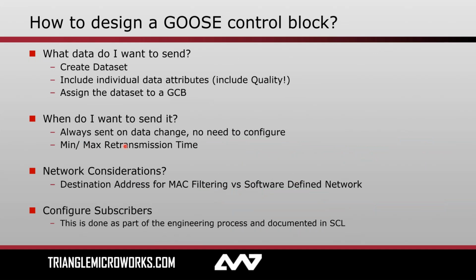So now let's talk a little bit about, like we did for report control blocks, what do you need to do if you're someone coming in and designing a substation, designing the GOOSE in it? What are the things that you need to keep in mind? Well, first, just like we had for reports, you need to design your data set. What information do I need to accomplish my larger goal? What are my protection schemes? Who's responsible for detecting the fault? Who's responsible for opening the breaker? Make sure that I include the data in the data sets that will be needed in order to accomplish those tasks. And then include the relevant data attributes. And please include quality. And then assign them to GOOSE control blocks.